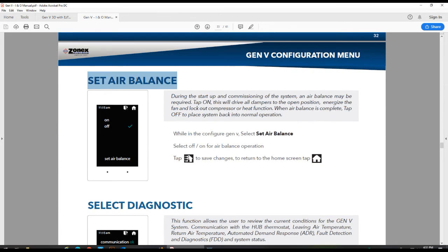Air balance. When you're ready to air balance the system, go ahead and place it into the on position. When you do this, it will send out a global call to open up all the dampers and bring the fan on, which in turn will then allow you to balance your butterfly dampers and your bypass. And then once you're done, go ahead and place it in the off position.